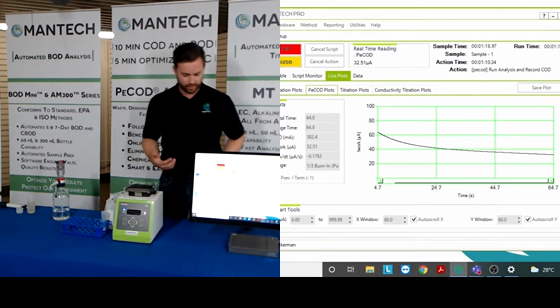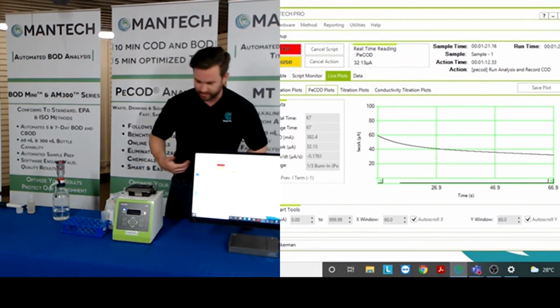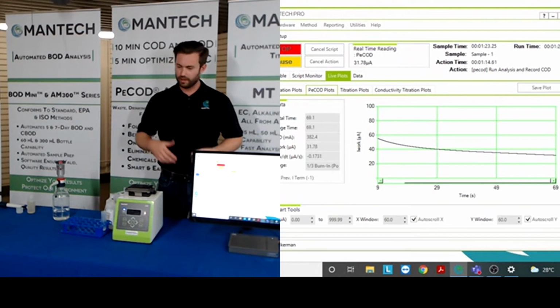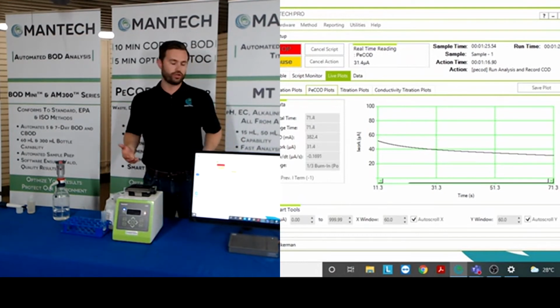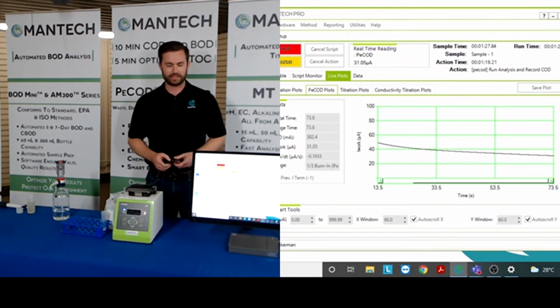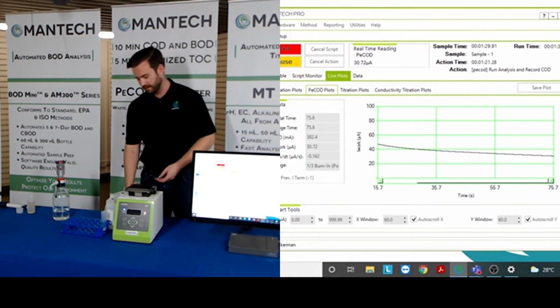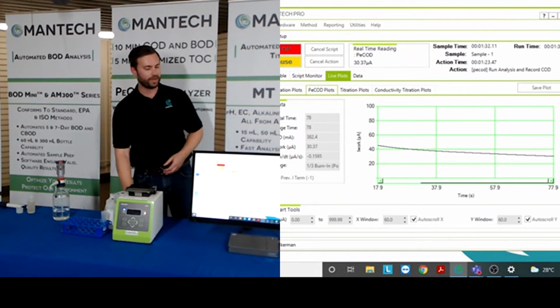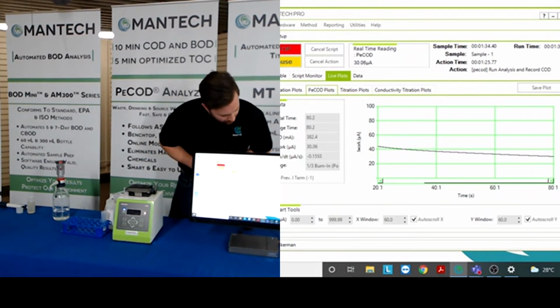So you can have your oxidation curve going for your blank, and then it's going to perform the sample oxidation, back calculate the total charge generated, which is proportional to the COD with a high degree of accuracy. And it's all done really simple and quick and really easy.